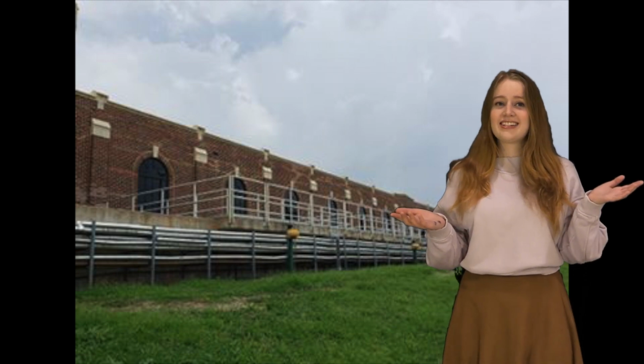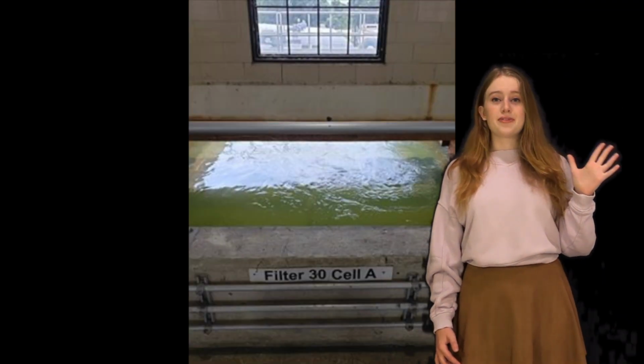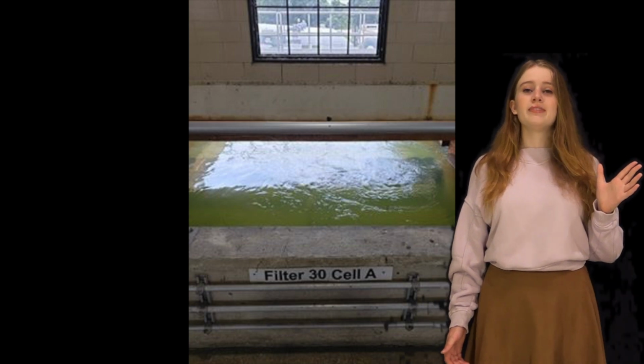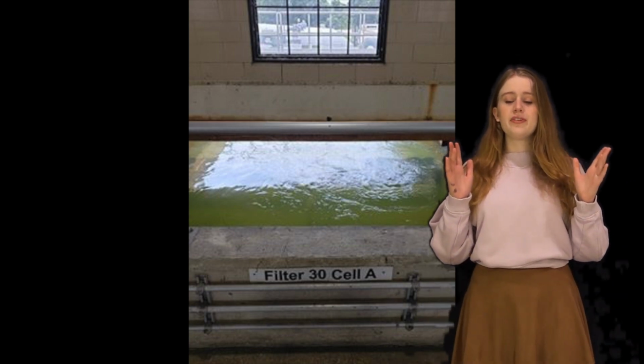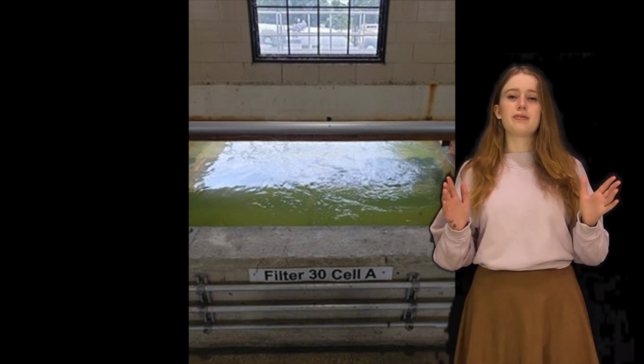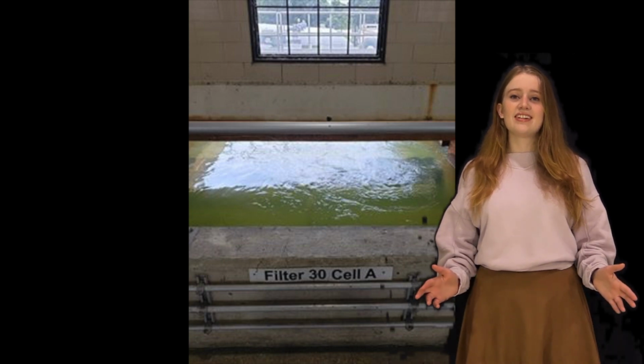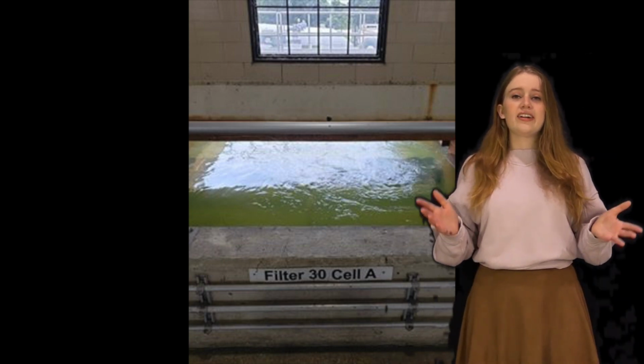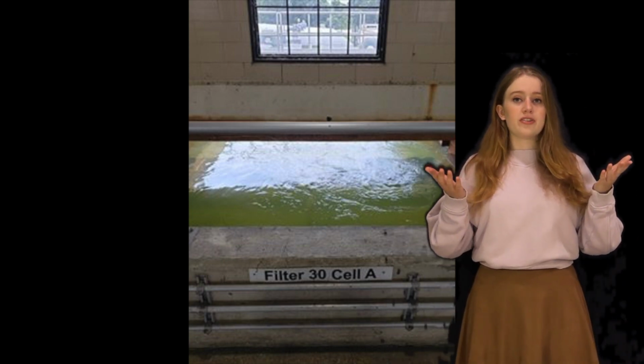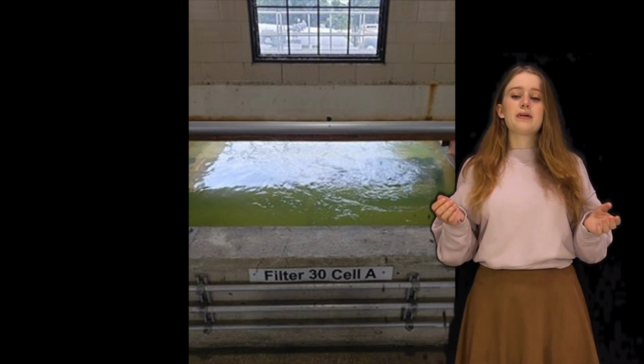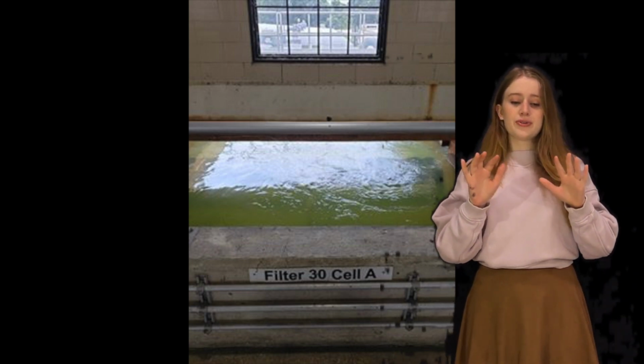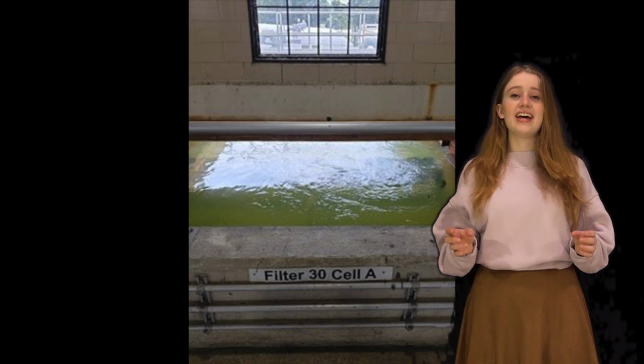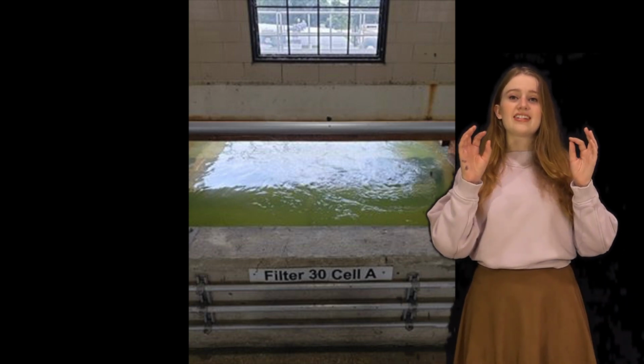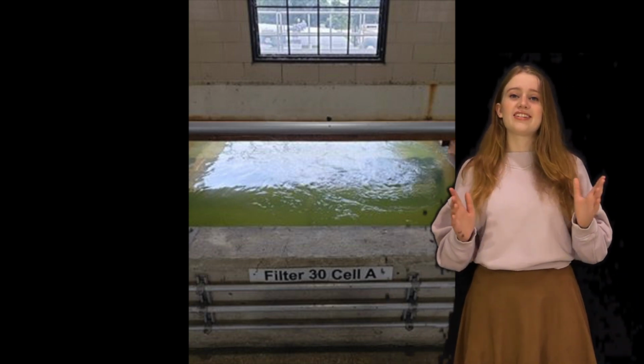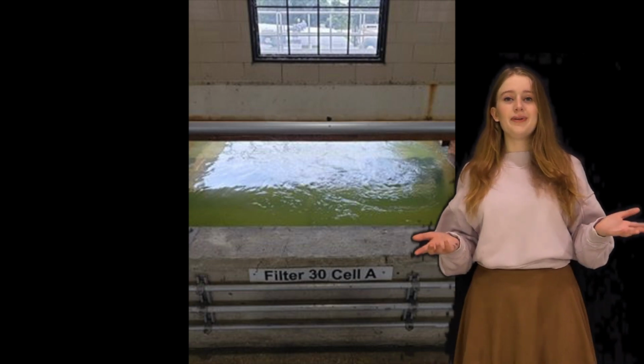The fifth step of the water treatment process is called filtration. Here, the water is put through a filter of anthracite coal and approximately 18 inches of sand, in order to strain all remaining particles out of the water. This is because as the water goes through the anthracite coal and then the sand, the particles will get stuck in the tiny holes even though the water easily flows through, leaving you with purer water.